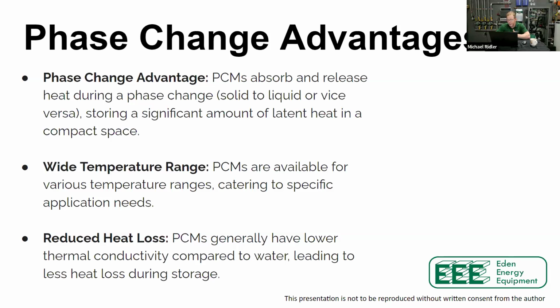The other nice thing about PCMs is they come in a variety of forms. The construction of a PCM battery is very proprietary and specific. It needs to be in a completely sealed canister, and it has to hold onto its moisture. There are a lot of chemical properties that go into the battery to make sure it can phase change back and forth between liquid and solid over a wide temperature range and over a long period of time. So when specifying a PCM battery, you choose one that phase changes at 43 degrees C, around 110 Fahrenheit, or you could do 55 degrees, 58 degrees, or much higher. In commercial applications, you'll see PCM batteries larger than the room I'm sitting in, phase changing at 176 degrees. It really comes down to what you need.